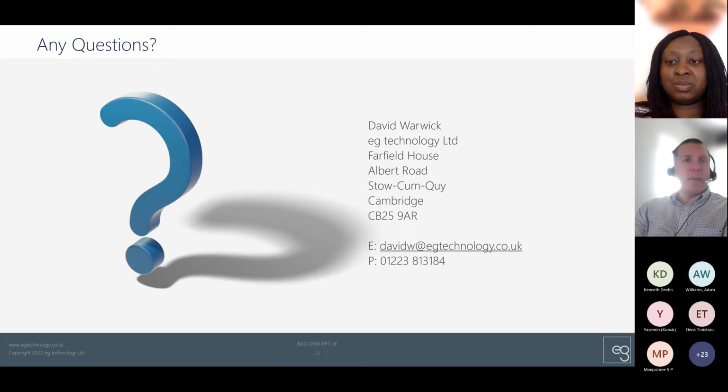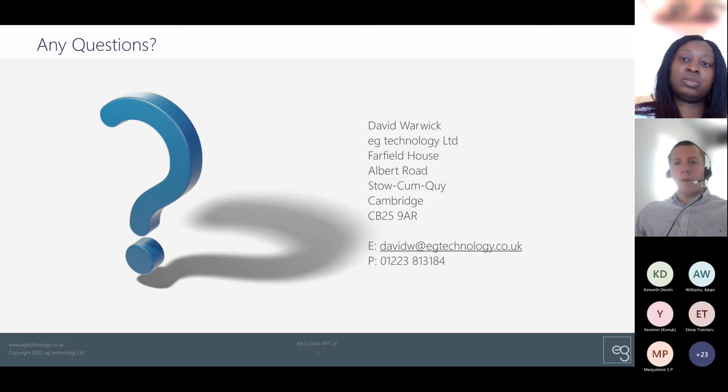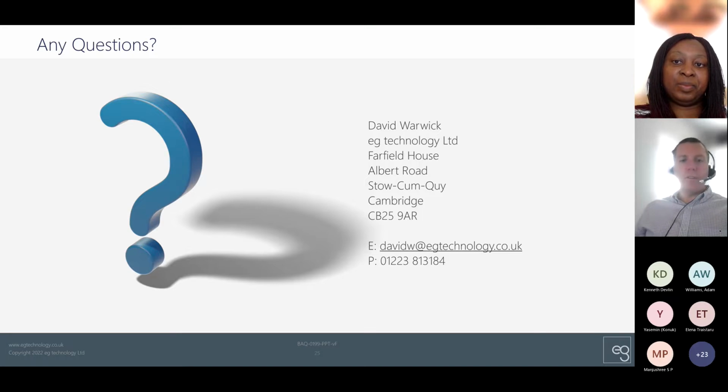So again, in the same way as getting the software architecture right early on, I would encourage anybody who is early in their product development journey to get some early stage regulatory advice. That might be an hour or two's chat with a regulatory consultant, or maybe it extends into a day or two of mapping out the processes that you need to follow. There are two dual pathways that you will eventually need to think of. One is that as what's called the legal manufacturer, you are going to have quality systems in place to govern everything that you do and the supply of your devices. And then there is the regulatory pathway for the actual device itself and how you design and develop a device that is safe and can be CE marked, UKCA marked.